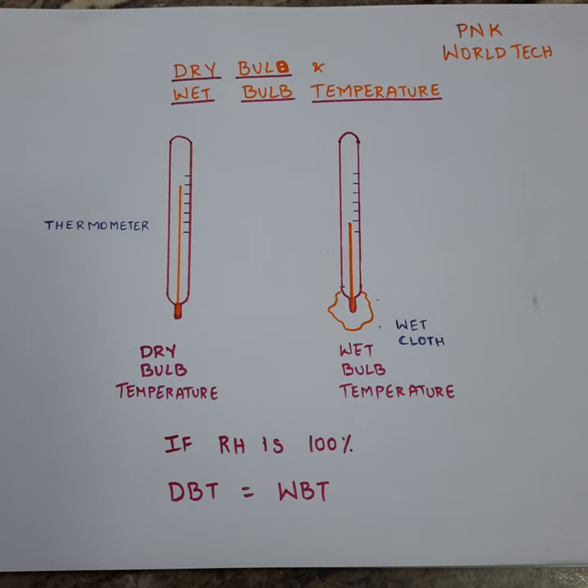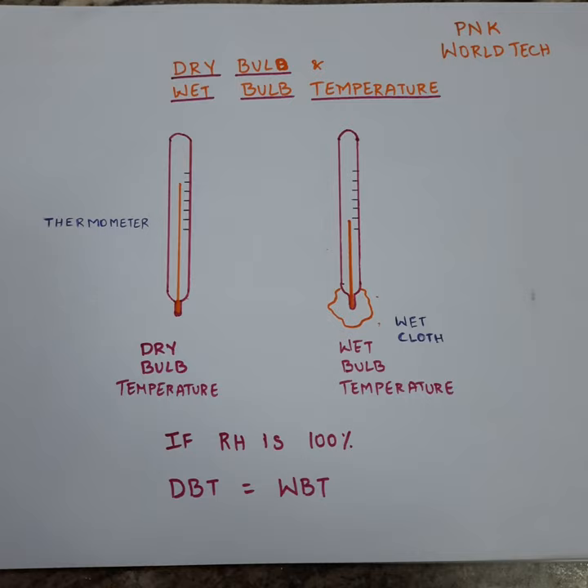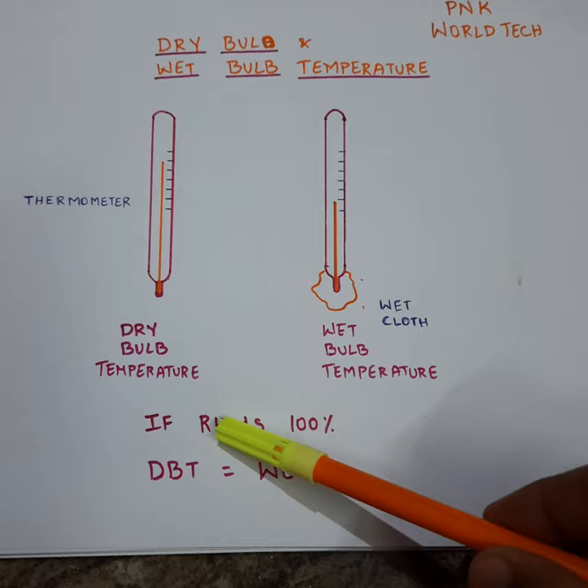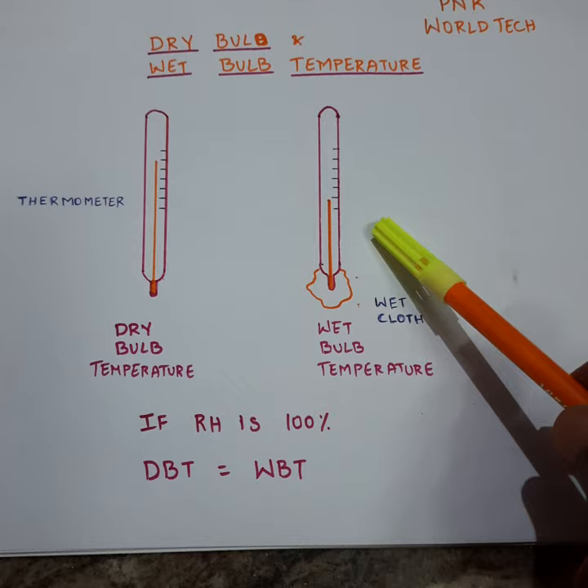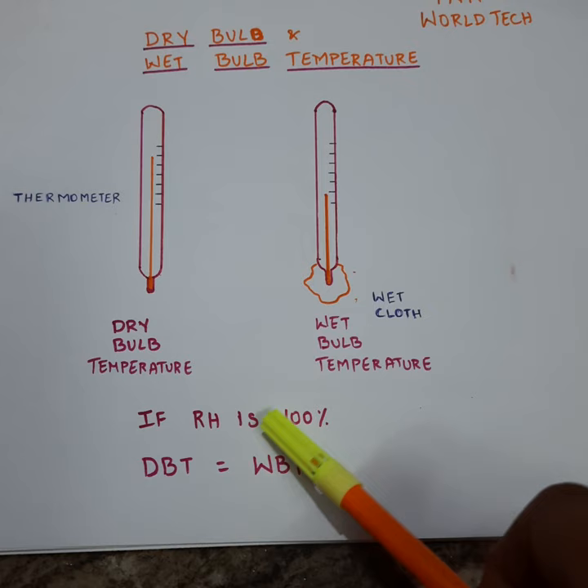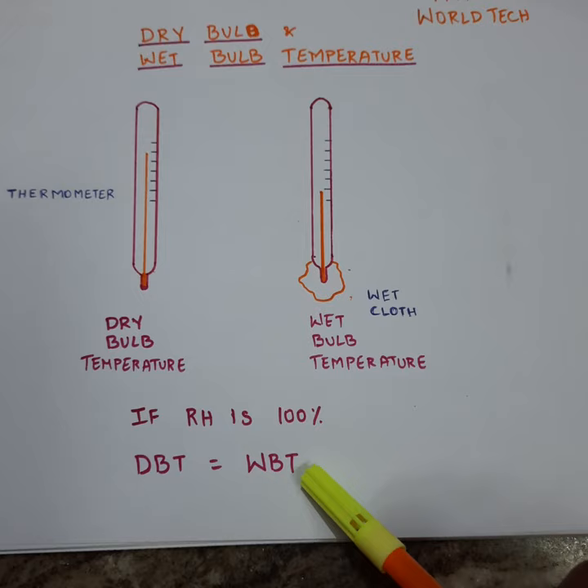This exercise helps us to estimate the relative humidity of air. If the relative humidity is high, the difference between dry bulb temperature and wet bulb temperature will decrease. So if the relative humidity is 100%, we can say that dry bulb temperature is equal to wet bulb temperature.